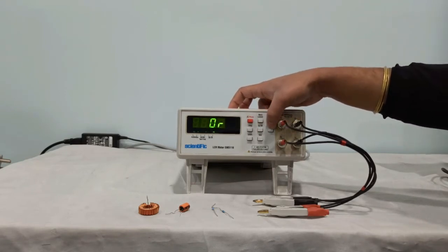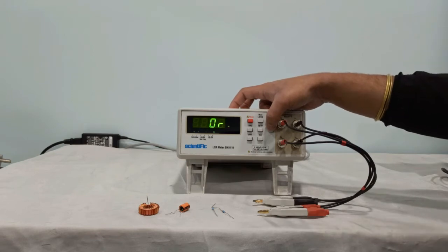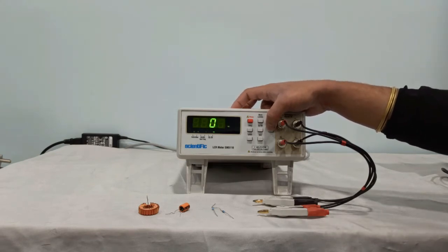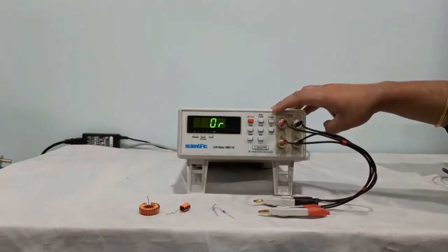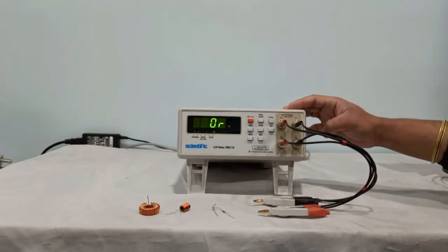Next is CAL switch. This is for probe compensation. This is used for zero compensation. You will have two compensation modes: open and short.